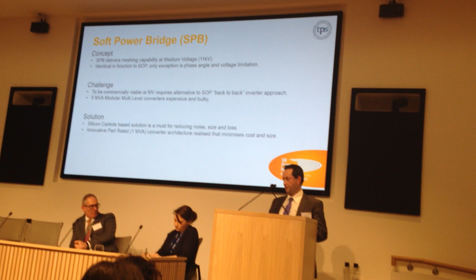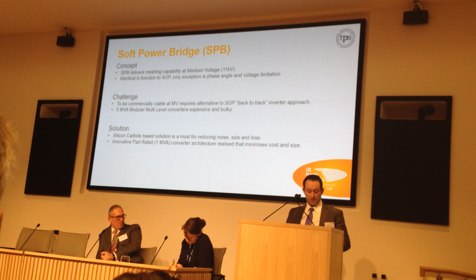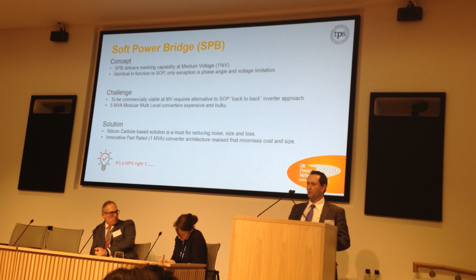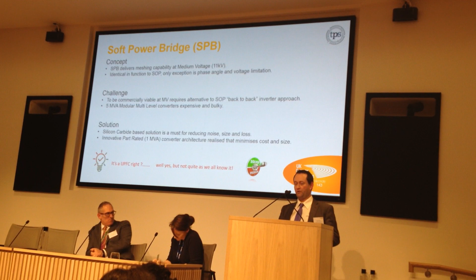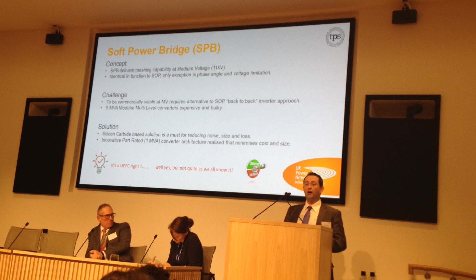So we came up with a novel architecture that allows us to use a part-rated converter to do effectively a 5 MVA link. So it's only a 1 MVA rated piece of electronics. So you're probably thinking right now, that's a unified power flow controller, right? Actually, yes, it is. It's fundamentally a unified power flow controller. Difference being, we've put a different architecture. We've come across a different architecture for this device, so it is quite novel in many ways. So I talked about that phase and voltage angle limitation. So I'm going to talk a little bit more about that.